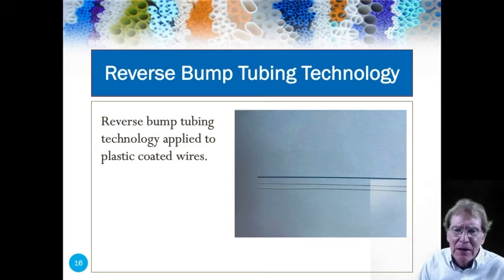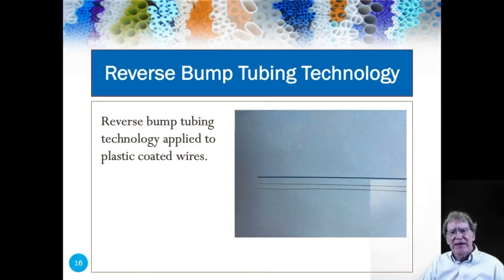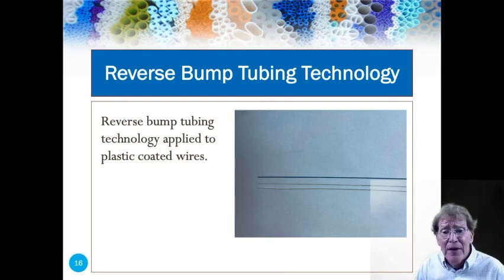Reverse bump tubing technology — people ask me what this is. It's when we maintain a constant outside diameter on the tube and vary the inside diameter from end to end. We've applied this technology to coating GI guide wires. The middle wire in the image is a bare wire, and you can see that it tapers down from roughly 20 thousandths of an inch down to 4 thousandths of an inch. Our reverse bump technology allows us to maintain a constant outside diameter of the plastic that jackets this tube from one end to the other, which allows the wire to be used in the GI system without poking holes in the sides of the intestines.